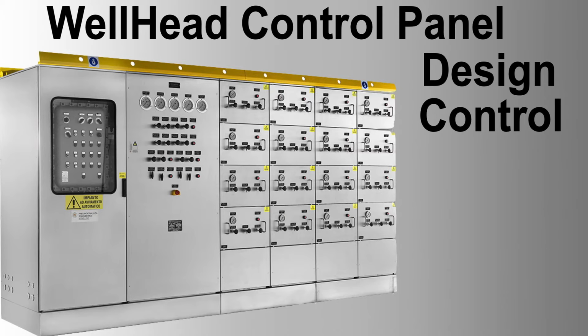2. Temperature control loop. Function: controls the temperature of the injection fluids or the wellhead. Control device: temperature sensor, heater cooler. Operation: the temperature sensor measures fluid temperature and sends feedback to the PLC RTU, which adjusts the heater or cooler to maintain the set point.